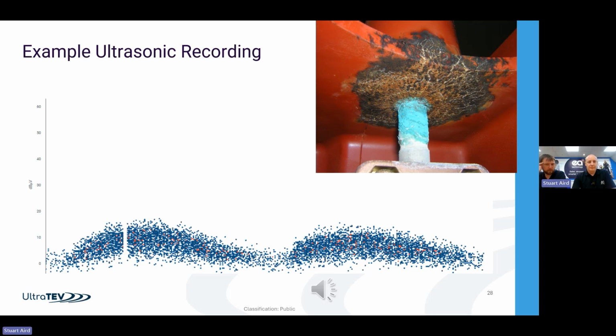Well, it's worth saying at this point, Stuart: ultrasonic readings, probably about 70% of what we find PD-wise is ultrasonic based. Those sound files, to the trained ear, are very clearly RPD, they've got the randomness in there, etc. But they aren't that easy to distinguish on site, and it's really hard to train people in that manner. So you'll find the device has got a built-in classifier, very accurate for airborne approaches, and that will classify whether it's PD or not. So you haven't got to go to that level of training, and I think it's a key element of the device you should be looking for.